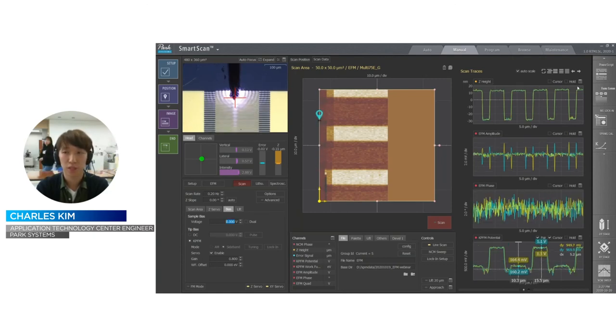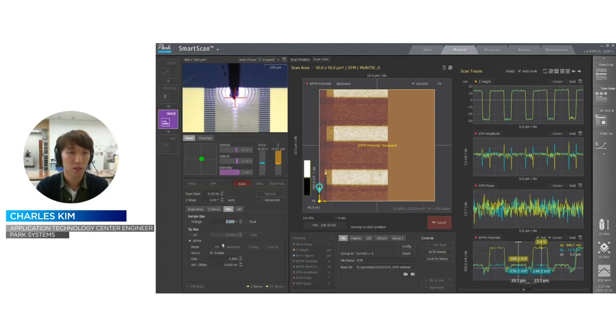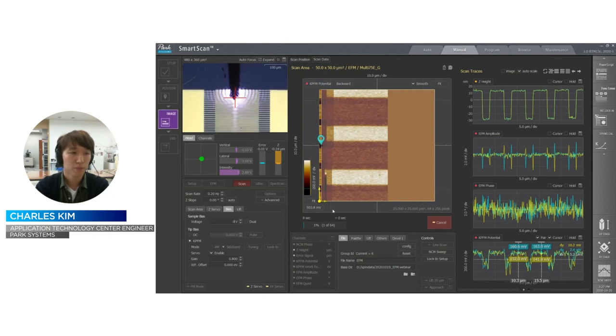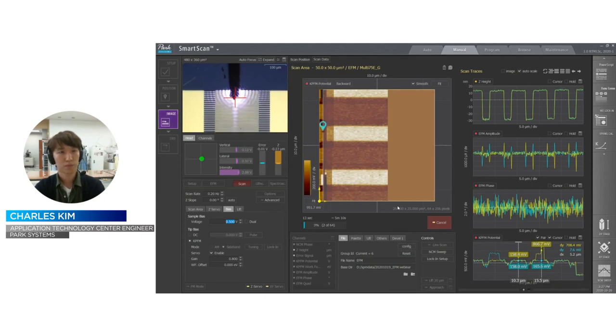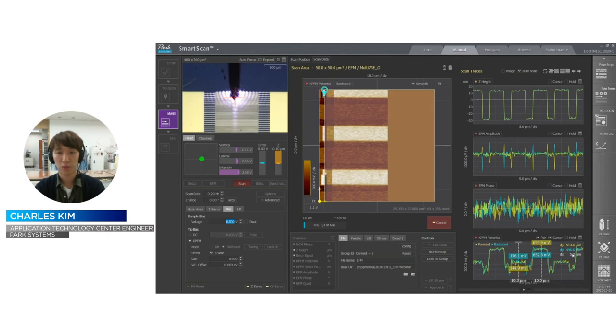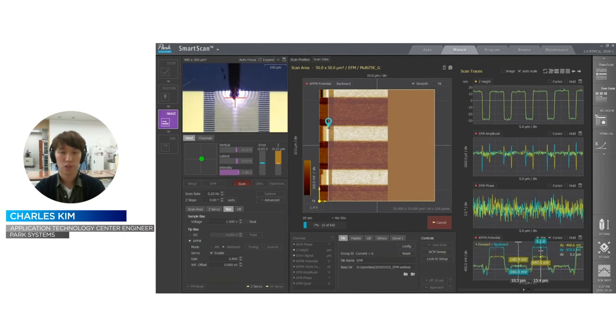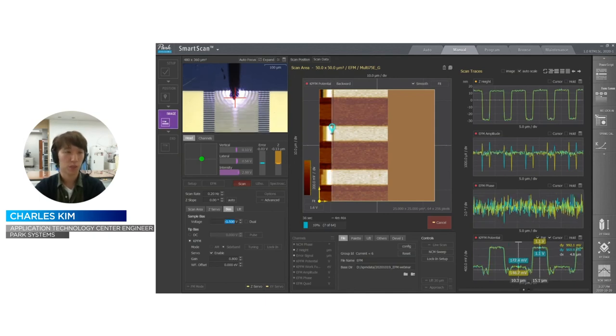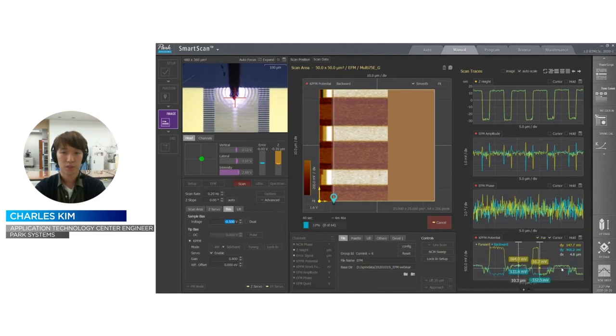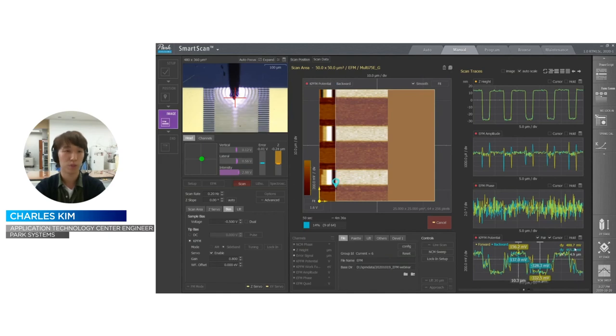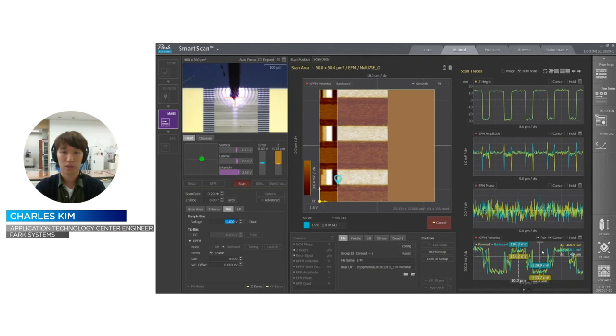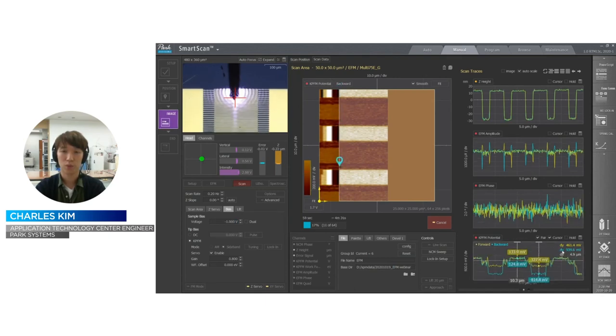So let's start the same measurement again. Then the values of the potential are 0.5 and 1. The potential value is almost close to 1 volt, like this, 999.8 millivolt. And if I change to minus 0.5, the difference between grounded and the minus 0.5 electrode is 500 millivolt, and minus 1 is almost minus 1 volt like this.